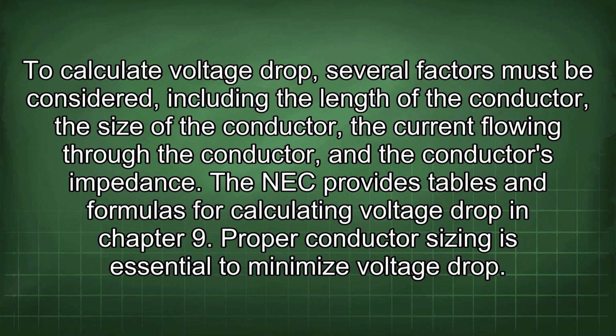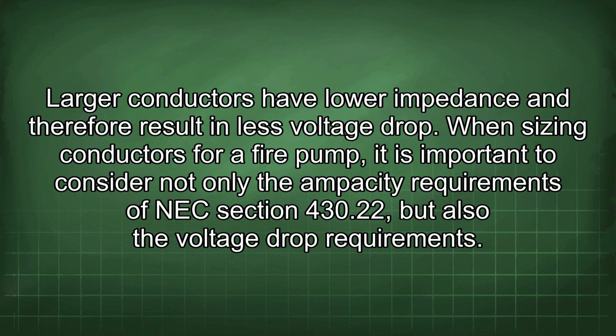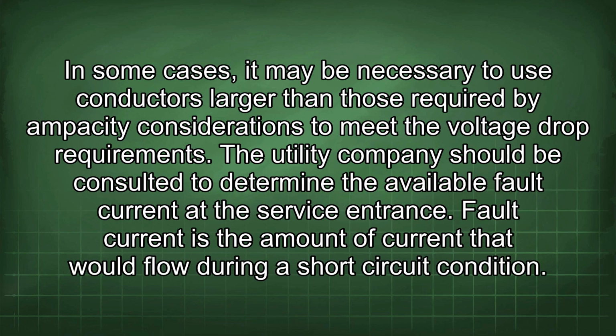Proper conductor sizing is essential to minimize voltage drop. Larger conductors have lower impedance and therefore result in less voltage drop. When sizing conductors for a fire pump, it is important to consider not only the ampacity requirements of NEC Section 430.22, but also the voltage drop requirements. In some cases, it may be necessary to use conductors larger than those required by ampacity considerations to meet the voltage drop requirements. The utility company should be consulted to determine the available fault current at the service entrance.